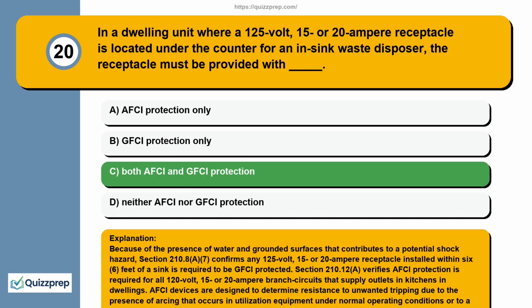Because of the presence of water and grounded surfaces that contributes to a potential shock hazard, Section 210.8(A)(7) confirms any 125 volt, 15 or 20 ampere receptacle installed within 6 feet of a sink is required to be GFCI protected. Section 210.12(A) verifies AFCI protection is required for all 120 volt, 15 or 20 ampere branch circuits that supply outlets in kitchens in dwellings. AFCI devices are designed to determine resistance to unwanted tripping due to the presence of arcing that occurs in utilization equipment under normal operating conditions or to a loading condition that closely mimics an arcing fault.